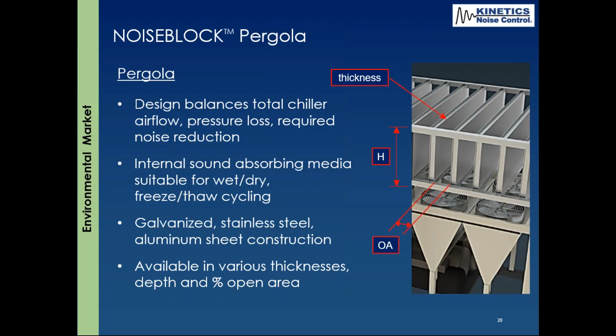We don't want to affect the performance of the chiller, so we balance the total chiller airflow, pressure loss, and required noise reduction. We do that in-house with our algorithms, helping the acoustical consultant model this. There's internal sound absorbing media, once again wet, dry, freeze-thaw - no bagging, you're in good shape there. It comes in different materials, various thicknesses, depths, and percent open areas. So that's our pergola.